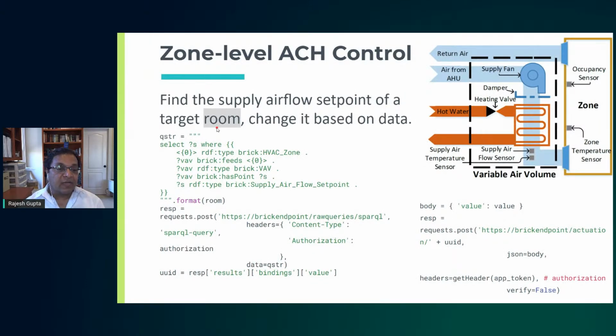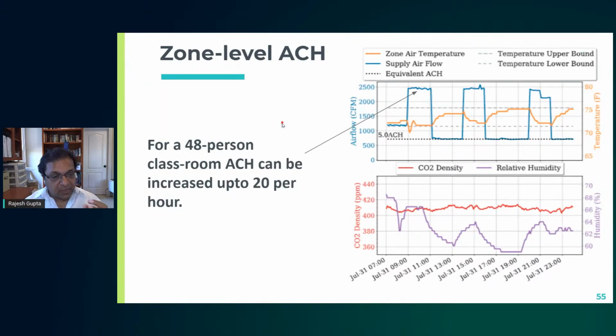So we asked the question: can you write a program that automatically goes through the entire air handling system of the building? It doesn't matter how many floors, hundreds of rooms, even thousands of rooms, and automatically identifies what the set point is, what the set point should be, and how much error. This is basically what this Brick program looks like. It does the set point detection of the stuck valves. But it goes further than that. It also says, for this period to this period, let's say every 2-hour interval before we meet, can I increase the air handling and then bring it back down? And how much can I increase it? It turns out that just for a classroom, we can go from 5 air changes to over 20 air changes.